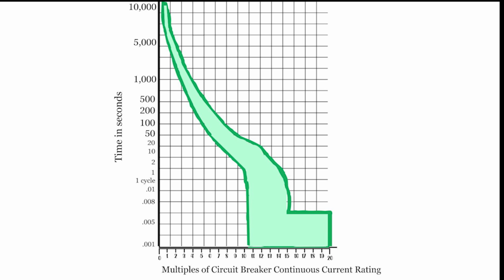And that top number at 10,000 seconds is not something I made up. That's legit. Under low current draws, it can take that long for those bimetallic strips to heat up enough to actually disconnect the circuit. And 10,000 seconds is a good long movie, so it's quite a while. On the lower end of the y-axis, where you see the 0.001, that area is almost considered the instantaneous trip of the breaker. So that's when you get in multiples of 20, 30, 40 times the amp rating of the circuit breaker. When the circuit breaker sees that huge amount of amperage, it almost instantaneously, via the magnet, disconnects the circuit.